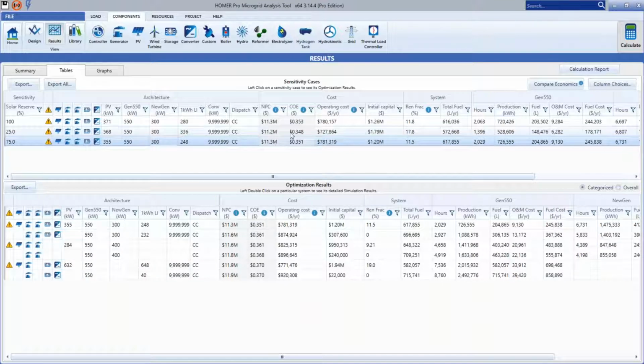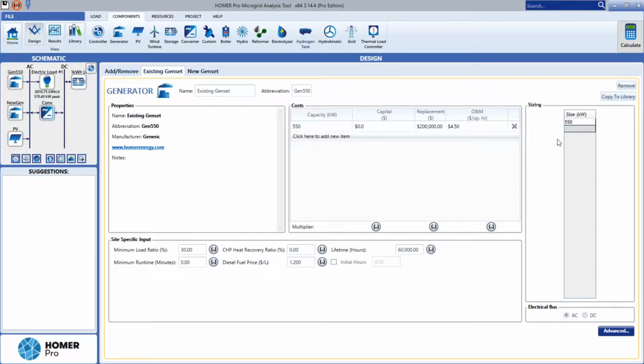And since we have specified that every time we run the system, we have to include the big genset, like the original genset, all the simulation will include that genset. So that means that genset will always be connected to the system. So in this case, there's no totally renewable energy system in our configuration. We can do that by reconfiguring the genset. So instead of having 550 only, we can have an option. What if we allow the system to not use any genset, just like the second genset that we have, we put here 0, just to explore what if we want to have a system that's purely running on renewables.